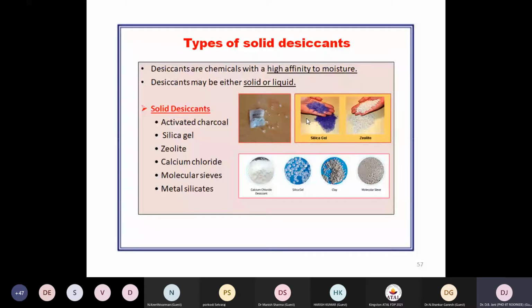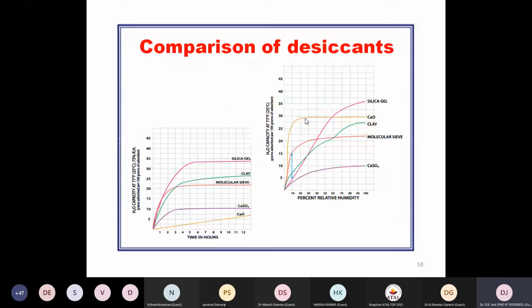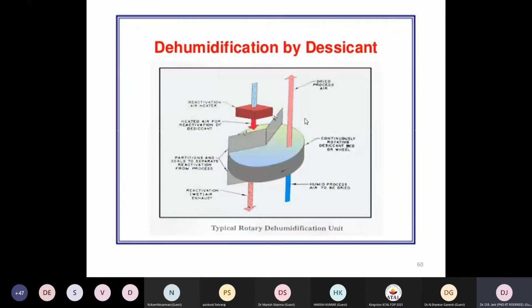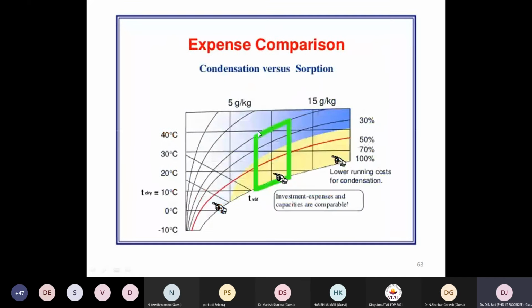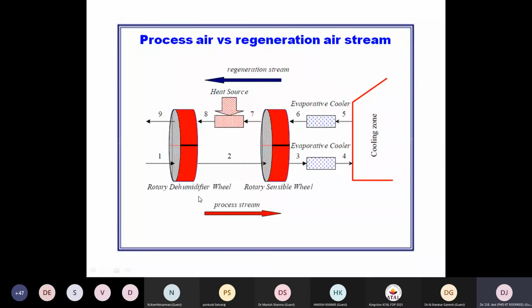A pictorial view will show the identification of the different desiccants in the industry too. This is the comparison performance chart for the use of different desiccant materials. Typically, a desiccant wheel is a rotary device whose section is divided into the process air and the reactivation air. After dehumidifying, we may provide a sensible heat recovery wheel for energy recovery, which can increase the effectiveness by lowering the temperature at the exit of the dehumidifier and by preheating the regeneration air supply to the reactivation side, so that the amount of heat source required will be reduced.